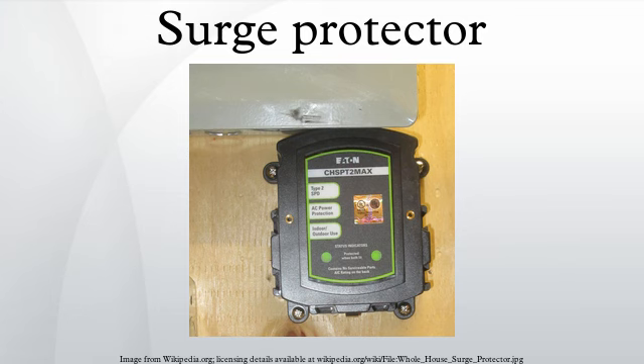It is often claimed that a lower joule rating is undersized protection, since the total energy in harmful spikes can be significantly larger than this. However, if properly installed, for every joule absorbed by a protector, another 4 to 30 joules may be dissipated harmlessly into ground. An MOV-based protector with a higher let-through voltage can receive a higher joule rating, even though it lets more surge energy through to the device to be protected. The joule rating is a commonly quoted but very misleading parameter for comparing MOV-based surge protectors.